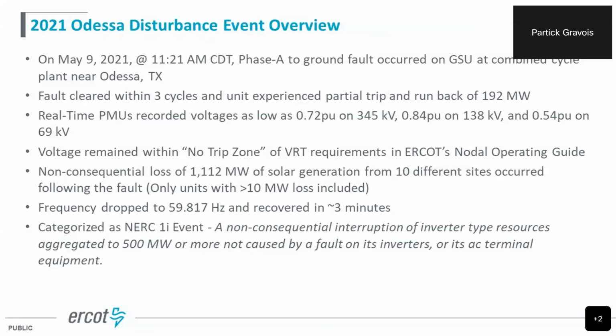So we had a non-consequential loss of approximately 1,112 megawatts of solar generation from about 10 different facilities. That's just counting the facilities that had at least 10 megawatt loss or more. There were several others that had a smaller loss, but we did not go that deep into it. It had a cutoff in order to get what we needed accomplished. There were some wind units as well, but we're going to focus on the solar because it was dramatically more than the wind resource losses.